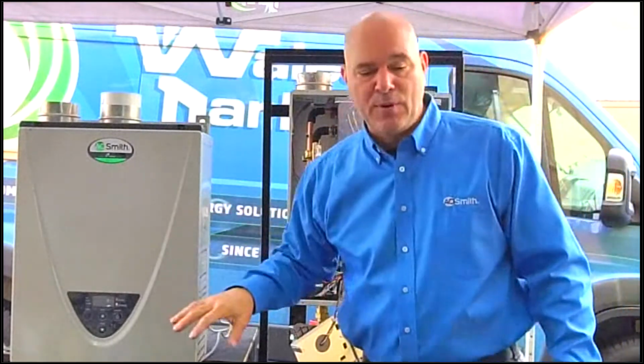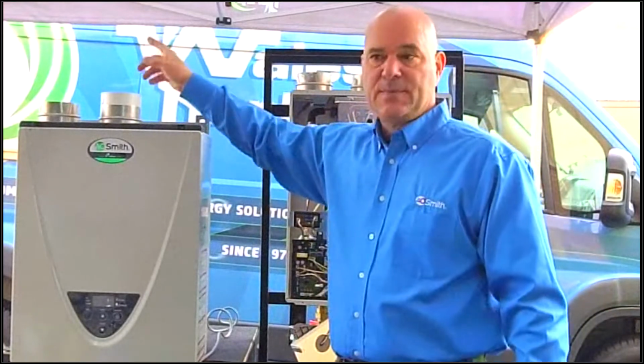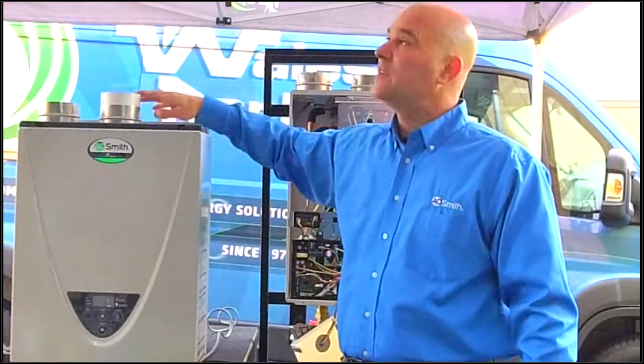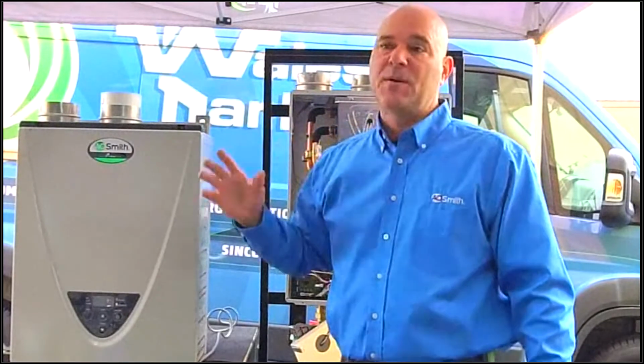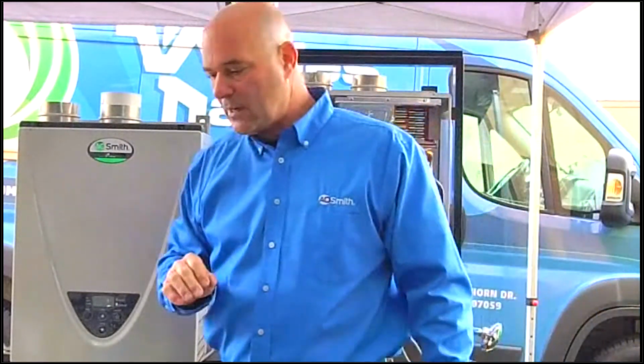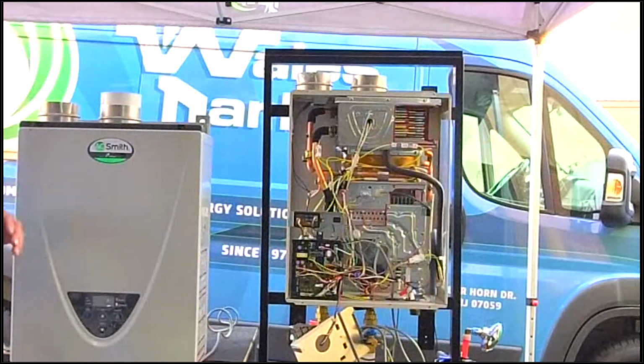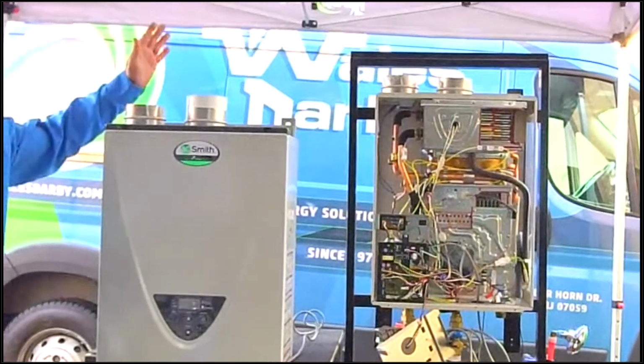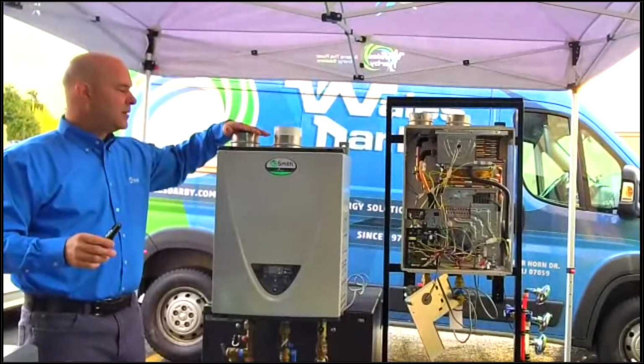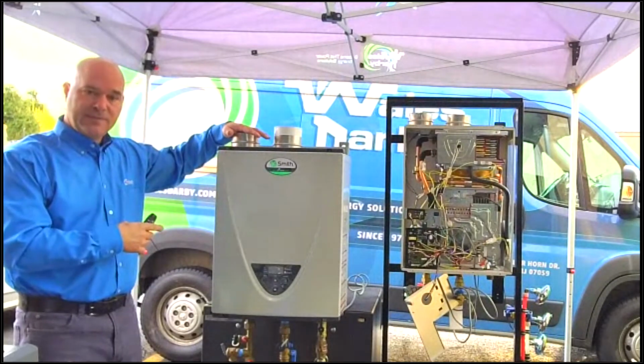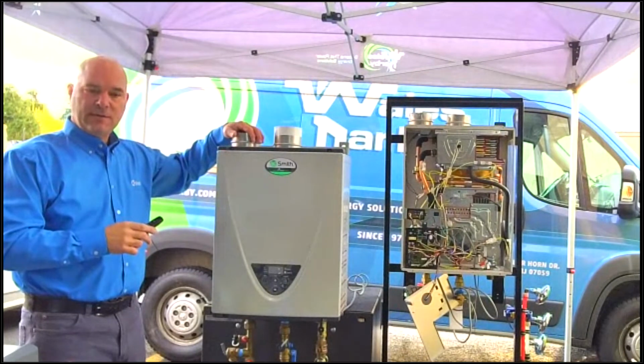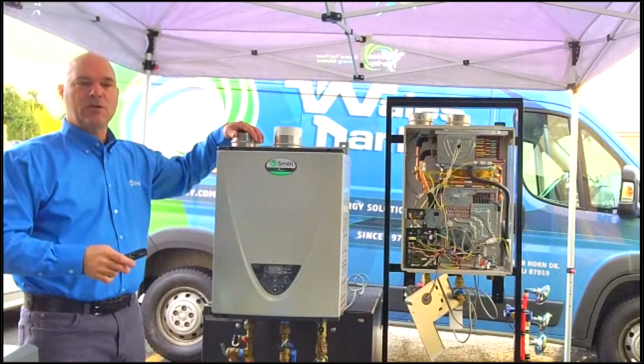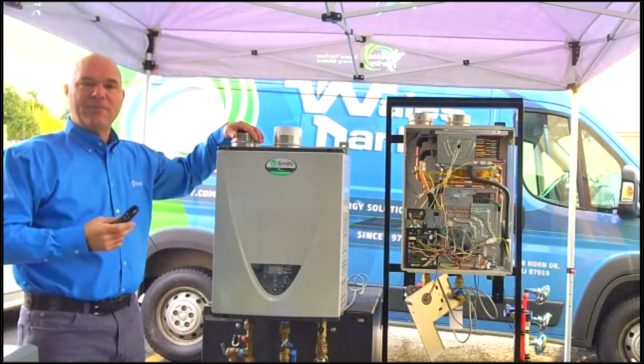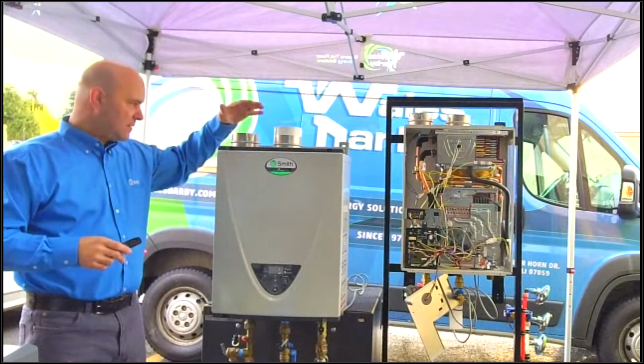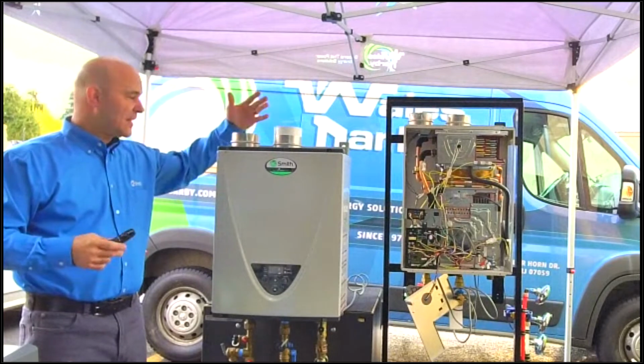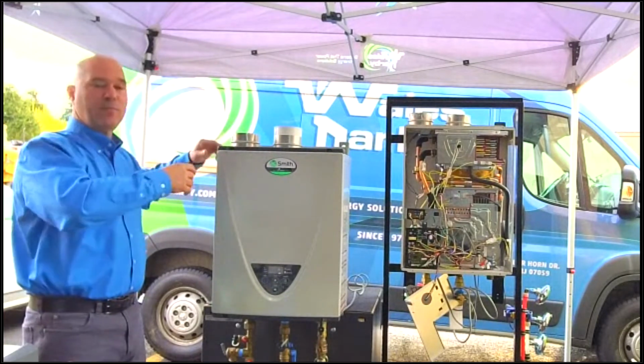These units, from a venting standpoint, can be vented 1 pipe, 2 pipe, side of the home, up through the roof, concentric, a bunch of different ways to vent them. Just keep in mind, and we run into this not often, but we run into it a bunch, where they'll want to vent with 1 pipe. Okay, great. But picture a 199,000 BTU unit. Picture the homeowner's basement being 2 empty 53-foot long tractor trailer beds. If you have that much space in the homeowner's basement, you're fine, 1 pipe, because they have enough air within the building to support combustion.